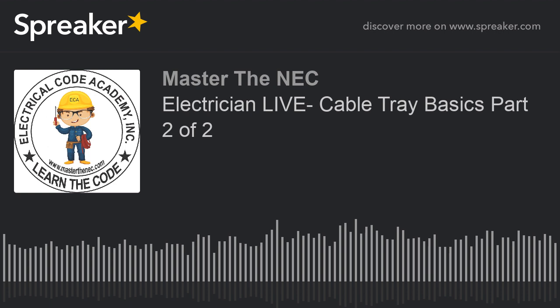The very last sentence makes it very clear. It exempts cables in a tray from these adjustment penalties, if you will, because, again, they don't have more than 3 current-carrying conductors. So, again, I get to forget that 310.15(B)(3)(a), or, of course, in the 2020 code, it's now 310.15(C)(1). It also reminds us that I'm not adding up all of the individual conductors in a tray. If I had to apply adjustments to this application, it would be based on the fact that I had more than 3 current-carrying conductors in that cable assembly. But if I don't have more than 3, I don't have to worry about it.